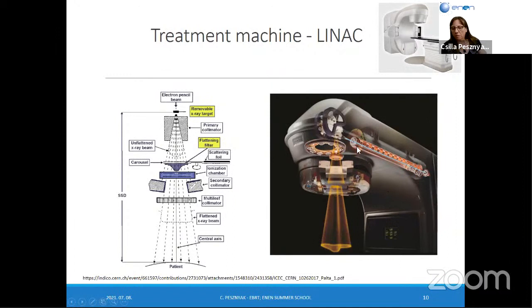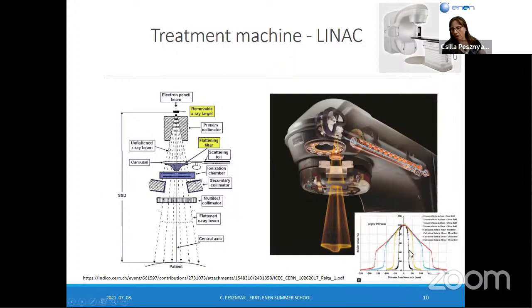You can see here the construction of the linear accelerator's head, and now you can see in a better view the head of the linear accelerator. It's the same as mentioned previously: ionization chamber, secondary collimator, multi-leaf collimator. You always have the flattened X-ray beam, and this part is the central axis and the patient. There are a lot of different scatter situations. And if I take out the flattening filter, before this profile was flat, and now we receive this shape of the profiles without flattening filters.